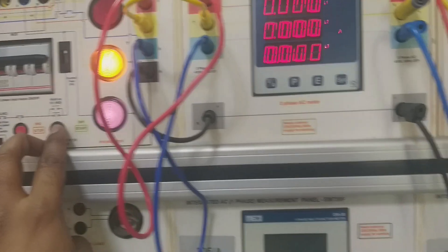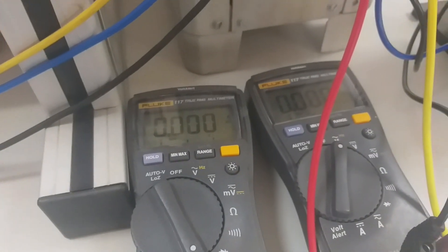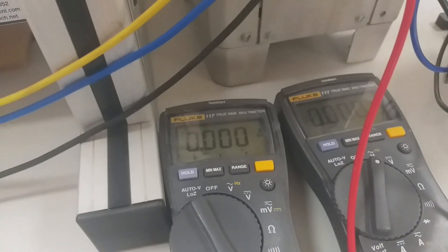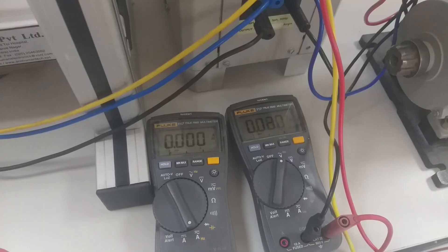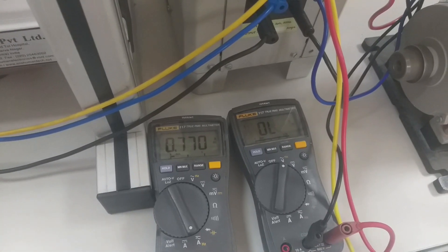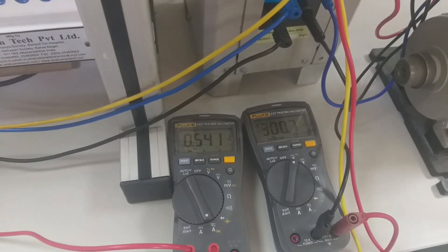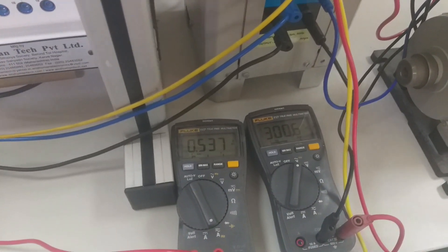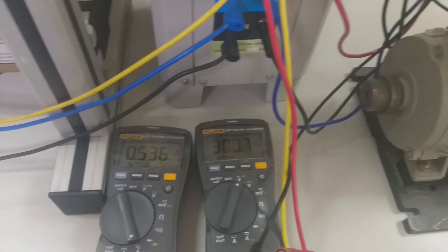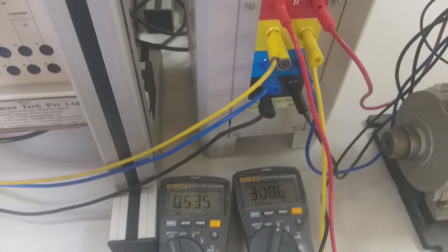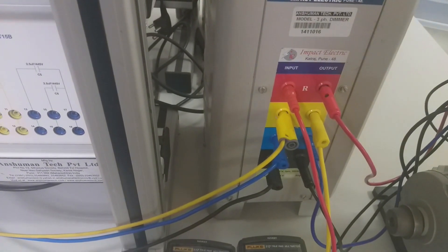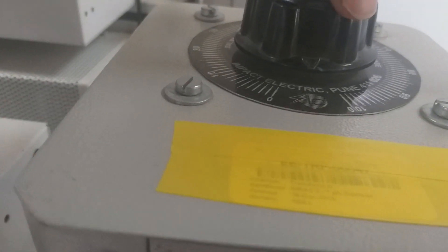So here I am going to start. We will see the current and voltage here when the motor is started with approximately 300 volts. This is inrush current, you can observe it. Now the value has reached a steady state value which is 0.53 amperes. It is almost 0.23 amperes less than the inrush current.